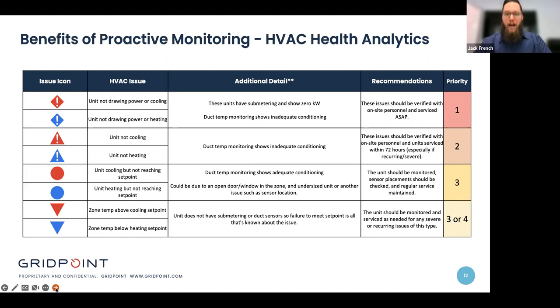I'm going to use the cooling analogy that we have been using since the beginning. If your cooling set point is, say, 70 degrees and what's coming out of the supply is 85 degrees because it's 95 outside, you're actually exacerbating that issue. You're making it worse by dumping warm air into a space that's already warm, and you're not providing cool air. If in turn the unit is not showing any power demand, then you can say there's probably a problem with the compressor. Maybe the fan is running, but there's probably an issue with the compressor. So we should go take a look at the compressor and resolve that as soon as possible.